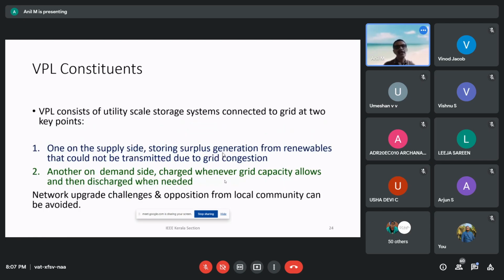So we have the VPL constituents. A VPL consists of a utility scale storage system connected to the grid at two key points. One on the supply side, storing surplus generation from renewables that could not be transmitted due to grid congestion. Another on the demand side, charged whenever grid capacity allows and then discharged when needed. Network upgrade challenges and opposition from the local community can be avoided. Here again, 100% extra capacity addition can be done if we convert a single circuit to double circuit, and we can increase the reliability of the transmission system. But then the local community opposition may be high, so a VPL, if we incorporate it, is an efficient solution for renewable energy integration.